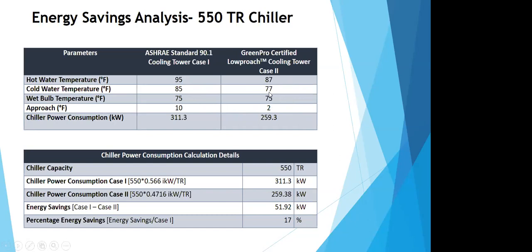So with this low condenser water temperature entering the chiller, we are able to reduce the power consumption of the entire chiller. From 311, we are coming to 259. This is almost 51 kilowatts of energy we have reduced by reducing the temperature of the condenser water. So in a nutshell, we see a saving of roughly 51 kilowatts, which accounts for around a 17% reduction in the energy consumption of the chiller by using the low approach cooling tower.